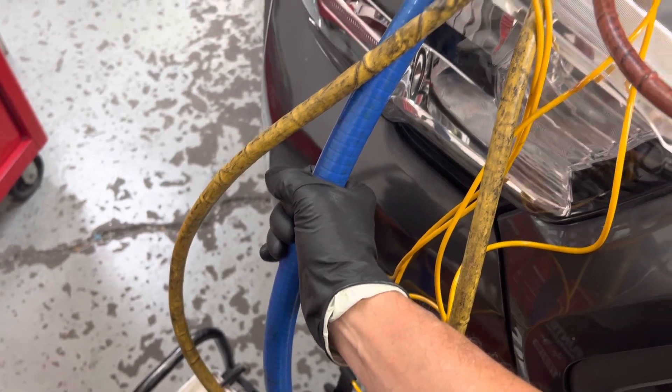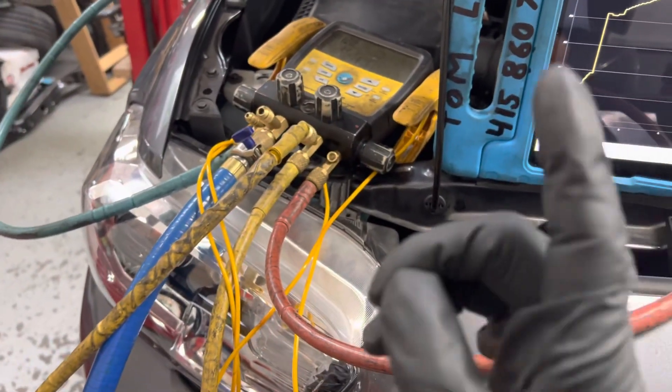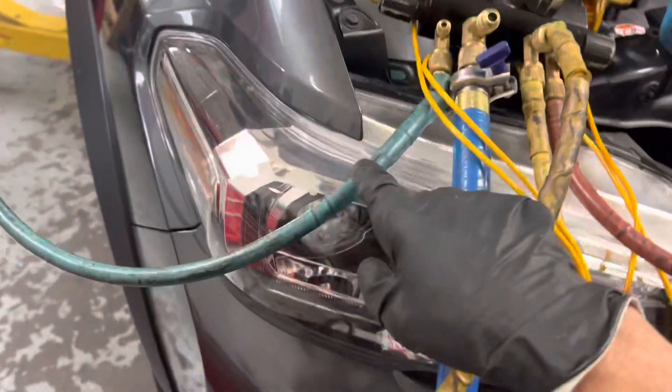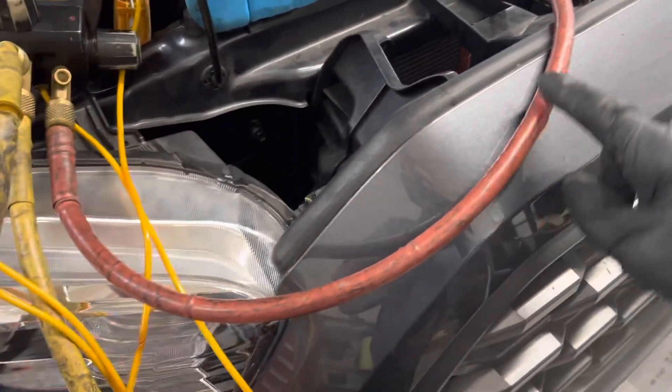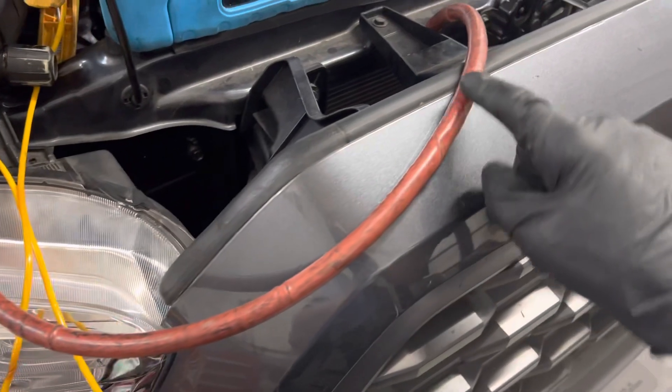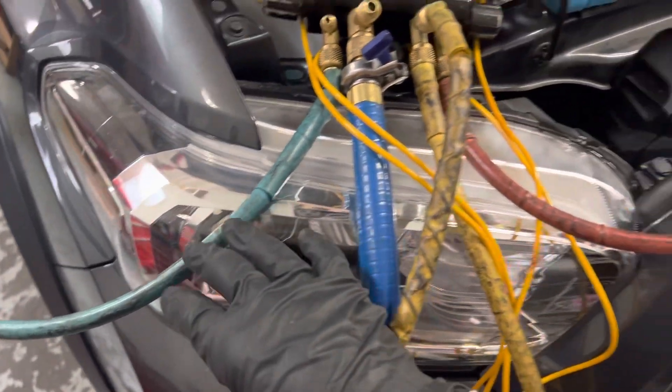This is a vacuum pump capable of three microns. This is a rubber silicone hose intended for vacuum use only - no refrigerant, no pressure, only vacuum. The weak link in the chain is the use of refrigerant hoses.